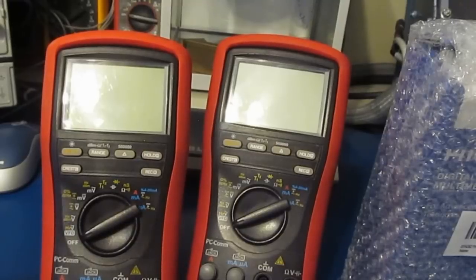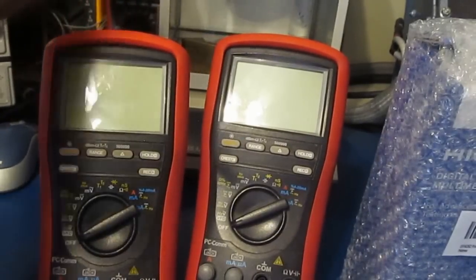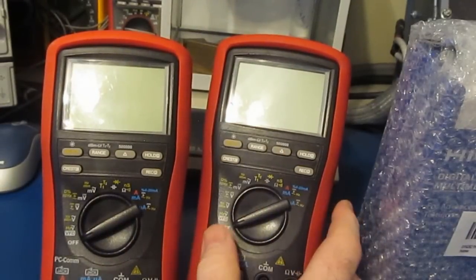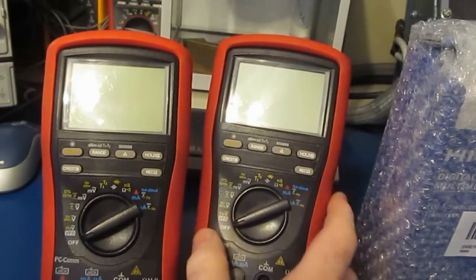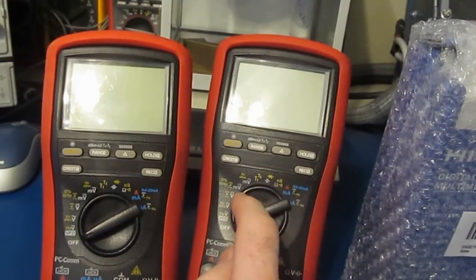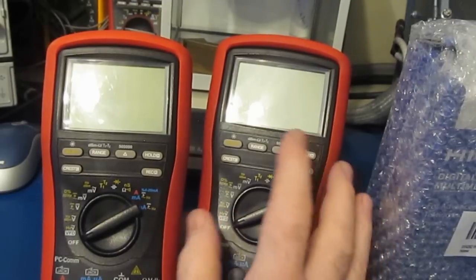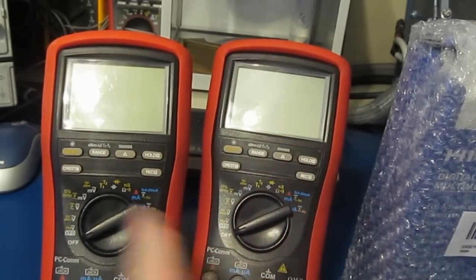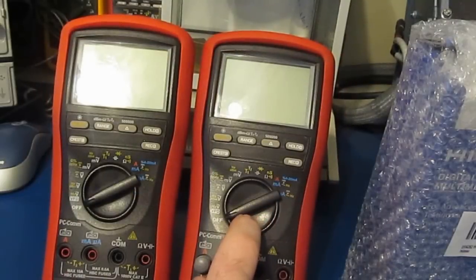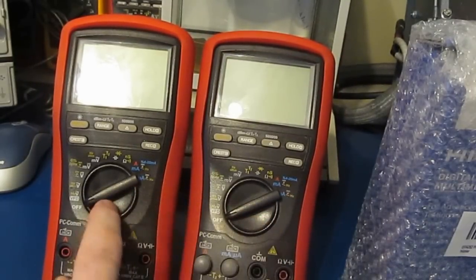So this meter has a few modifications, whereas this one was damaged at 10,000 volts peak with a 50 microsecond full width half height. I had repaired the meter using the OEM parts, so this meter is basically stock, where this one is not. While this meter is 10 years old, I'd have to go back and look, but this meter is probably in the order of maybe 7 years old.